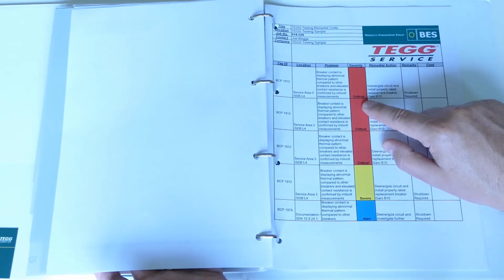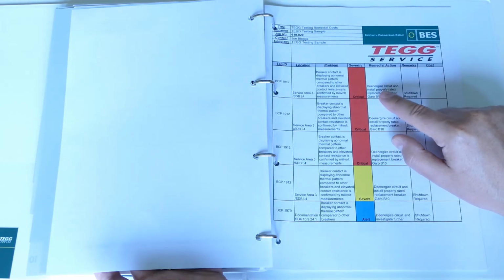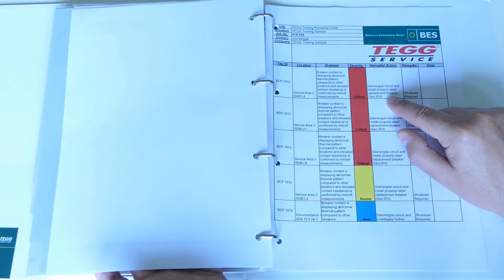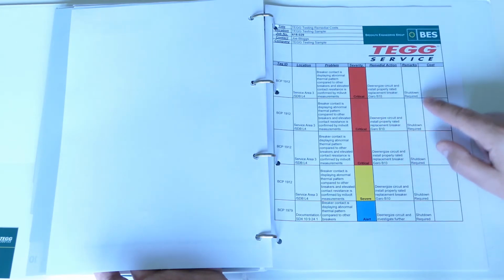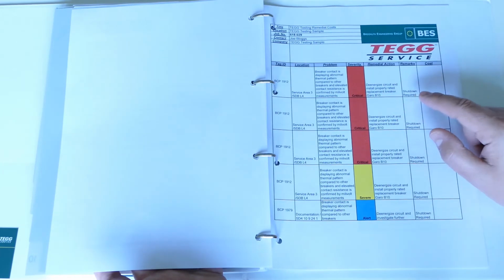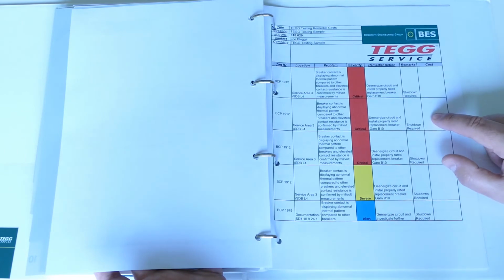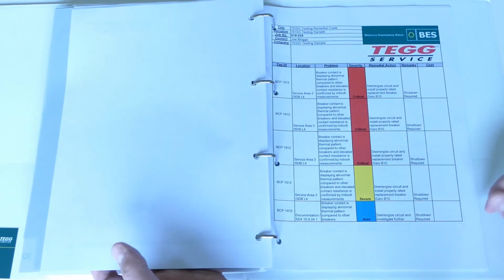It's considered critical, and we are recommending that you de-energise the circuit and install a properly rated breaker, a Garo B10 in this instance. A shutdown is required to make this repair, and there will be a cost beside each recommended repair, so it's an itemised breakdown.